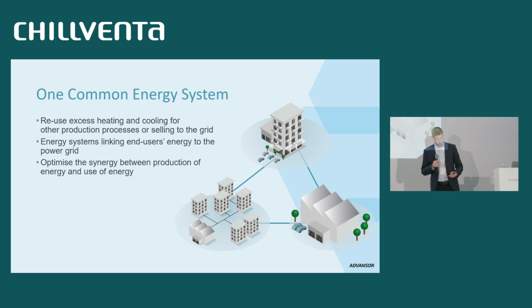When we see a heat pump, we need to collect the energy from somewhere to drive the heat pump. Actually, I see this as similar to what we have been doing in the refrigeration business for many years. When we have a refrigeration system, we have heat recovery, we recover the excess heat. Now when we have a heat pump, we need to look into the possibility to recover the excess cooling. For example, it could be a factory where we can use the excess cooling ourselves, or we could provide it or sell it to the grid, provide it to the neighbor building or whatever. So, linking up the energy between the buildings, and then also the power grid.